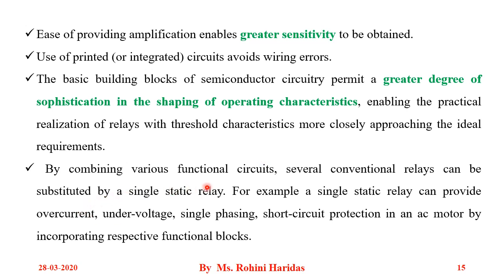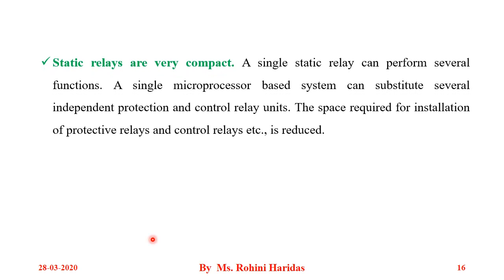By combining various functional circuits, several conventional relays can be substituted by a single relay. For example, a single static relay can provide over-current protection, under-voltage protection, protection against single phasing, and short circuit protection in an AC motor by incorporating the respective functional circuits. Static relays are also very compact — a single relay can perform several functions.